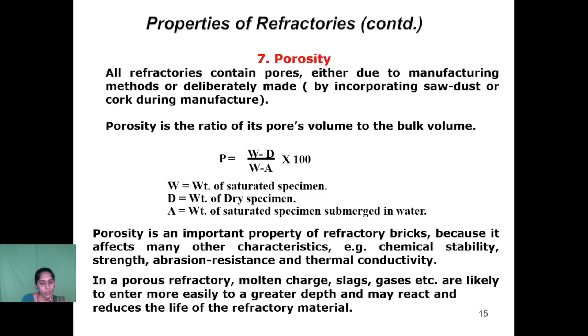Next one, porosity is an important property of refractory bricks because it affects many other characteristics, for example chemical stability, strength, abrasion resistance and thermal conductivity. In a porous refractory, molten charge, slags, gases, etc. are likely to enter more easily to a greater depth and may react and reduce the life of the refractory material. Next one, porosity. Porosity decreases its strength, resistance to abrasion, and resistance to corrosion or penetration by slags, gases, etc.